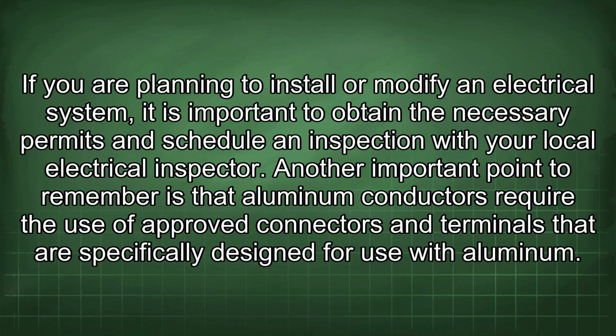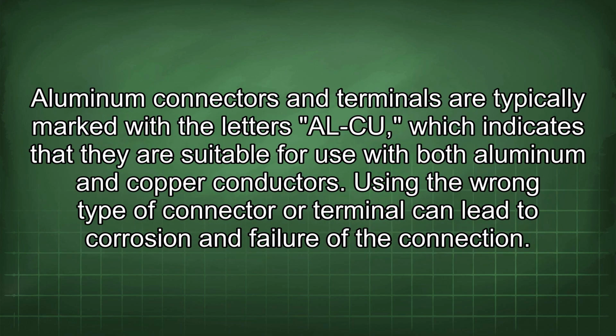Another important point to remember is that aluminum conductors require the use of approved connectors and terminals that are specifically designed for use with aluminum. Aluminum connectors and terminals are typically marked with the letters AL/CU, which indicates that they are suitable for use with both aluminum and copper conductors.